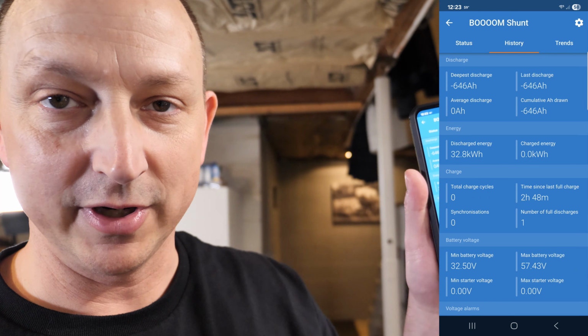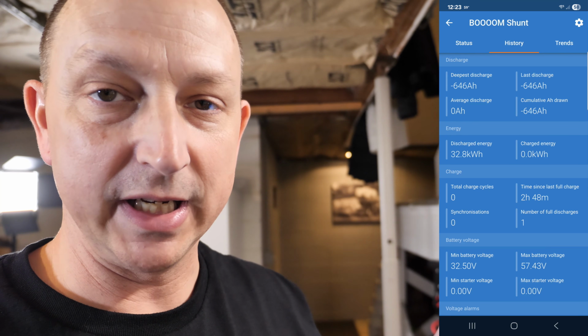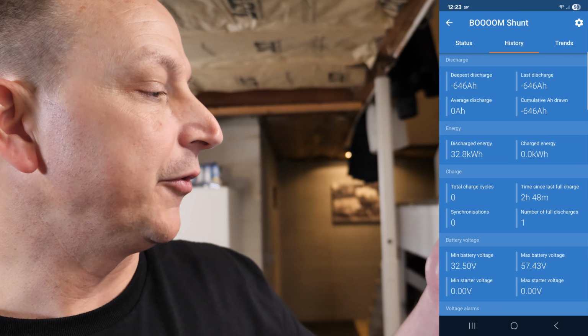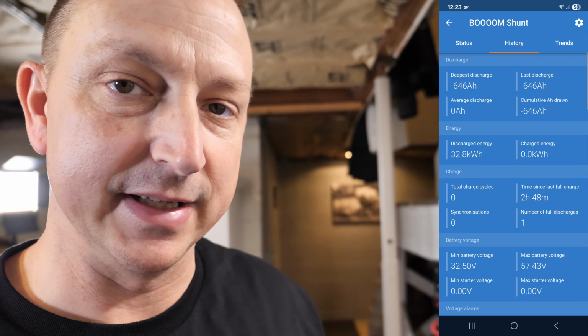646 amp hours according to the boom shunt, or 32.8 kilowatt hour. We ran for 2 hours and 48 minutes. Basically what this means is you can use one of these batteries to run your entire house, run it full throttle the entire time, and not have a problem. Of course, if you run it at 12,000 watts, you only get a couple hours runtime, but if you just run it normally, pulling like 1,000 to 1,500 watts constantly, maybe a little bit less at nighttime, you could really get by with just one of these batteries.